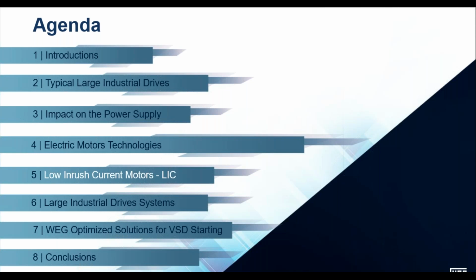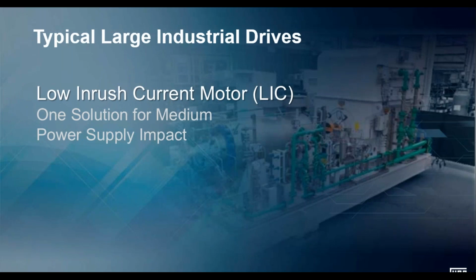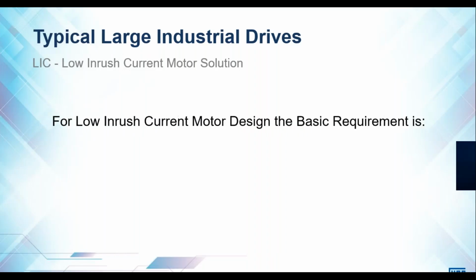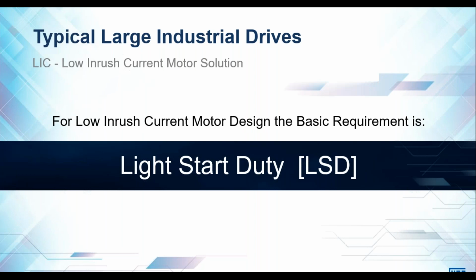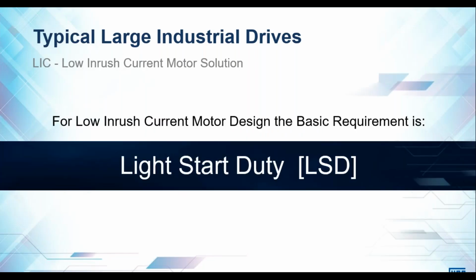All right, let's unpack the low inrush current design machines in a little bit more detail. So let's just define some requirements of where we can apply a low inrush current design motor. In essence, this is just an alternative to putting in some other starting device. It's really designing a standard squirrel cage motor to reduce the locked rotor current or the starting current to a medium impact level of starting current.